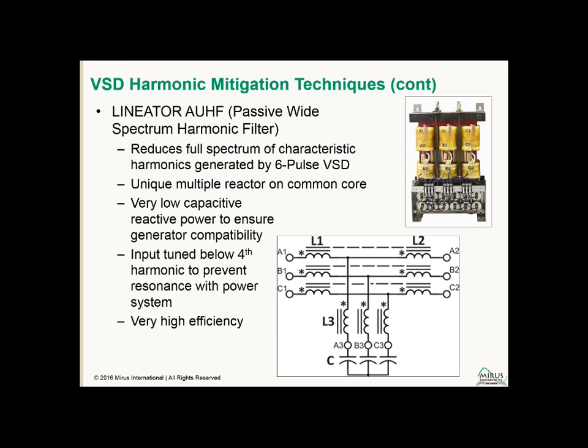So the best solution for treatment of harmonics is a passive wide spectrum harmonic filter, our Lineator AUHF. This filter reduces the full spectrum of harmonics generated by a 6-pulse variable speed drive. It has a unique reactor. It's built on a common core. The schematic shown here has a blocking reactor on the input, a compensating reactor on the output, and then a tuned branch reactor tuned with a capacitor.